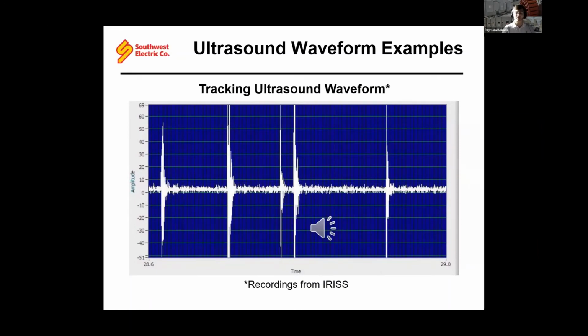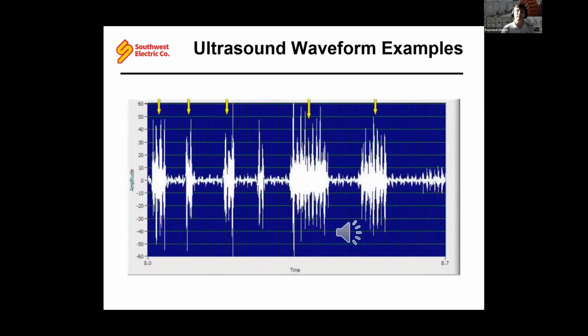So this means that there's a slow decay or slow breakdown of that insulation. And if that tracking continues, it would lead to a phase-to-phase or phase-to-ground fault and could cause significant damage to your equipment. This one happens to be actual arcing that's going on. Obviously, this is a serious situation you would want to act upon right away.